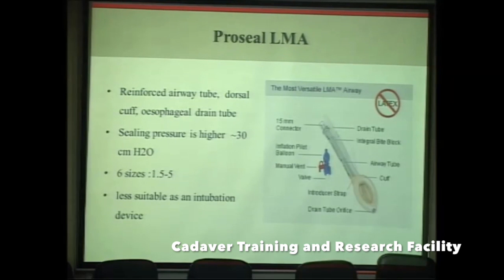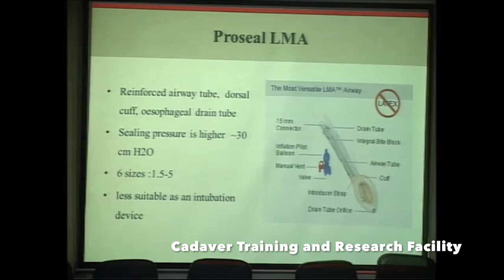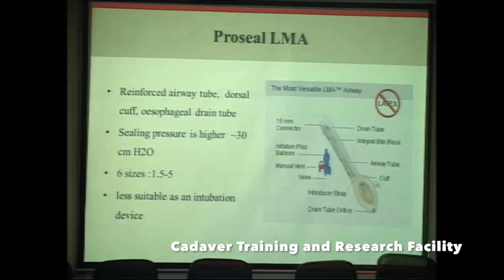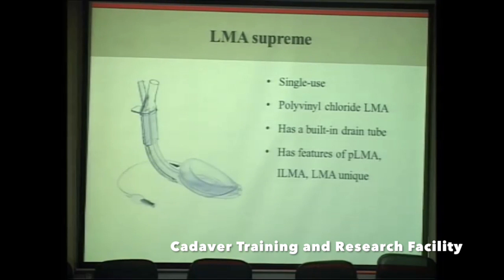The ProSeal LMA is the benchmark for second generation LMAs. It has a reinforced airway tube, an additional dorsal cuff, an esophageal drain tube, a cuff introducer strap, a manual vent, inflation pilot balloon, and an integral bite block. The pharyngeal sealing pressure is higher than the classic LMA at approximately 30 cmH₂O. It comes in six sizes from 1.5 to 5. The ProSeal LMA is less suitable as an intubation device.